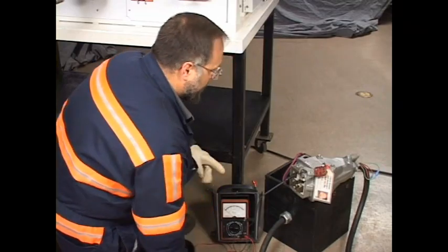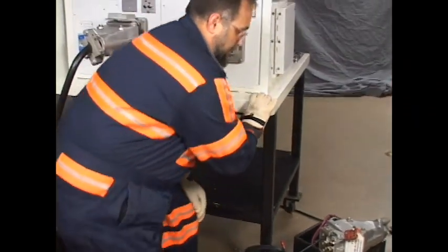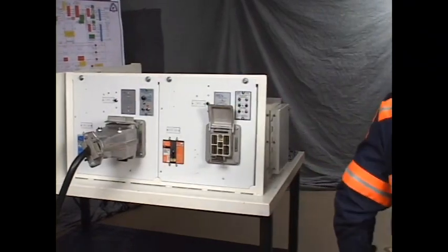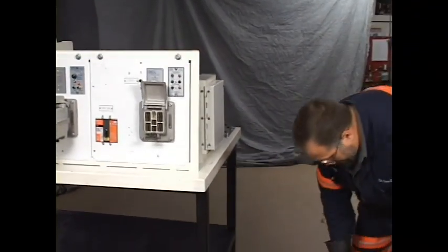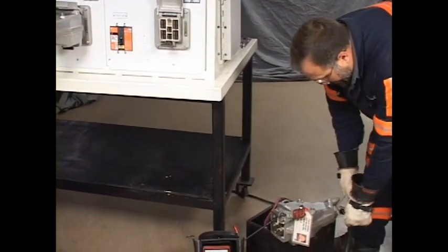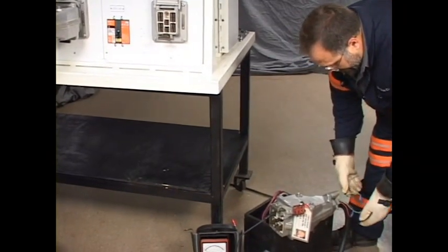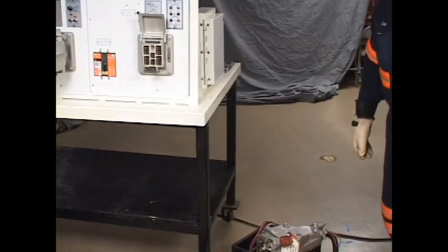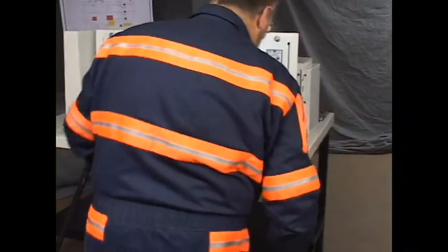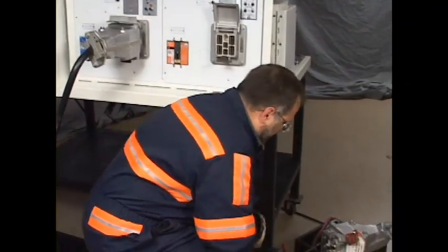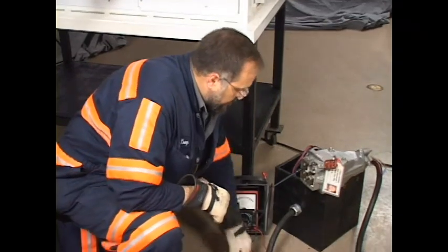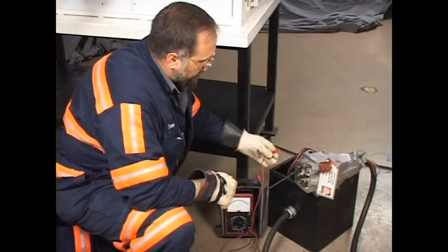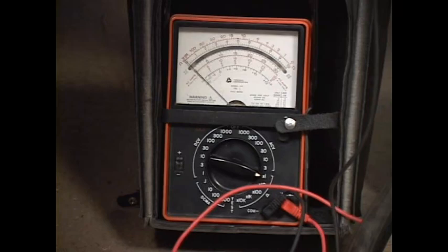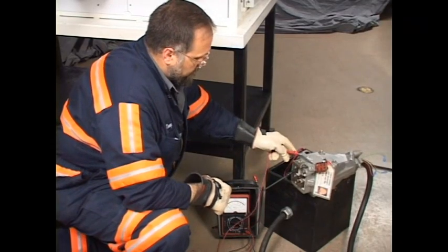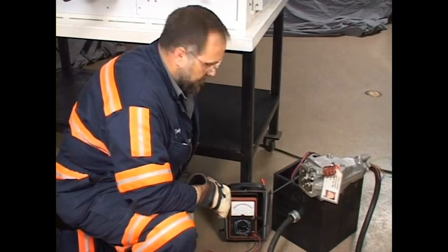Okay. Now, for the purpose of our training, I've made a connection at the rear of the cable coupler. This connection here will interrupt. I can use that to show you a proper reading. With the black lead attached to the ground blade, it should read an open circuit to the shell. As you can see, it does. An open circuit. Okay.